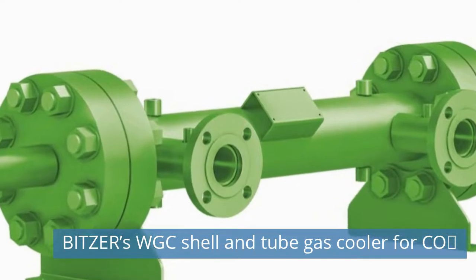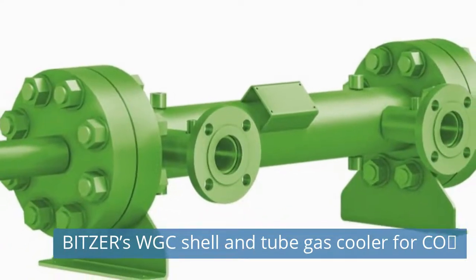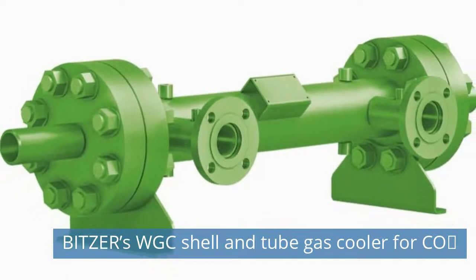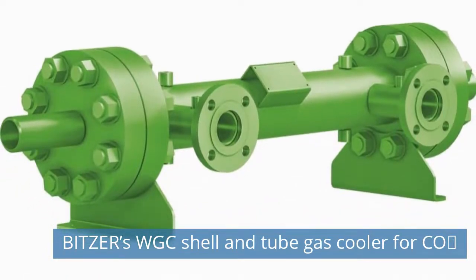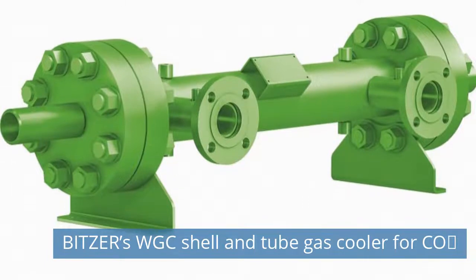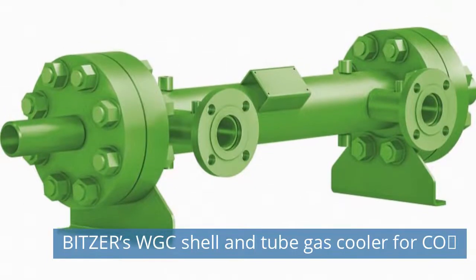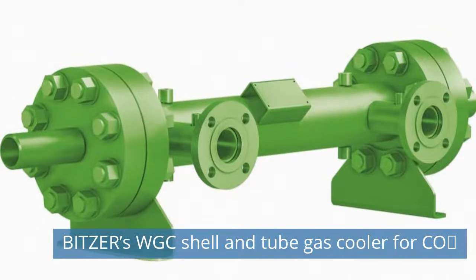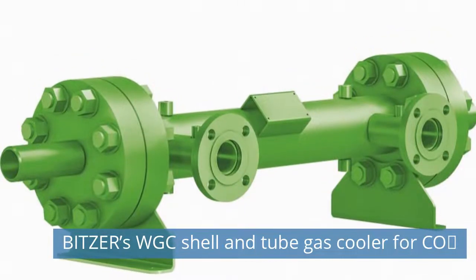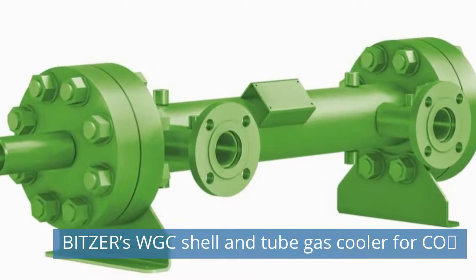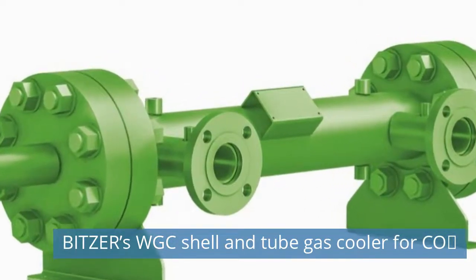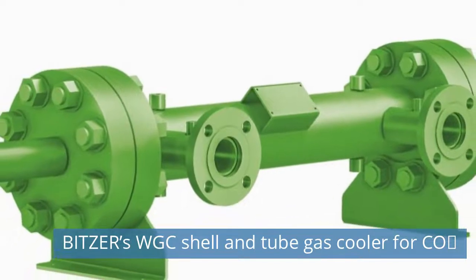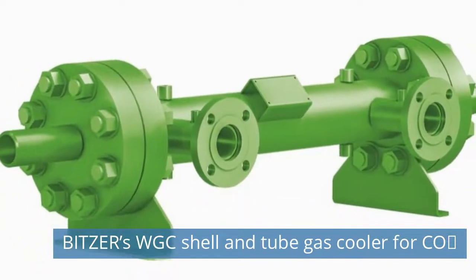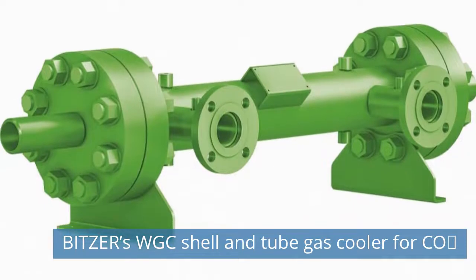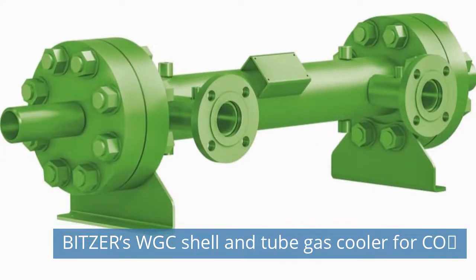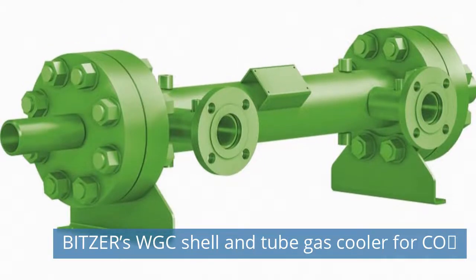Shells and tubes for good reason: WGC heat exchangers are based on the shell and tube design, which is highly resistant to both mechanical and thermal fatigue. Compared with other heat exchanger technologies, this design offers notable advantages for installations in water-cooled CO2 refrigeration systems, especially when the system has a medium or large capacity of more than 250 kilowatts. One single WGC can replace up to three brazed plate heat exchangers, making the system less complex to install. Furthermore, they offer high thermal efficiency thanks to their counterflow design.